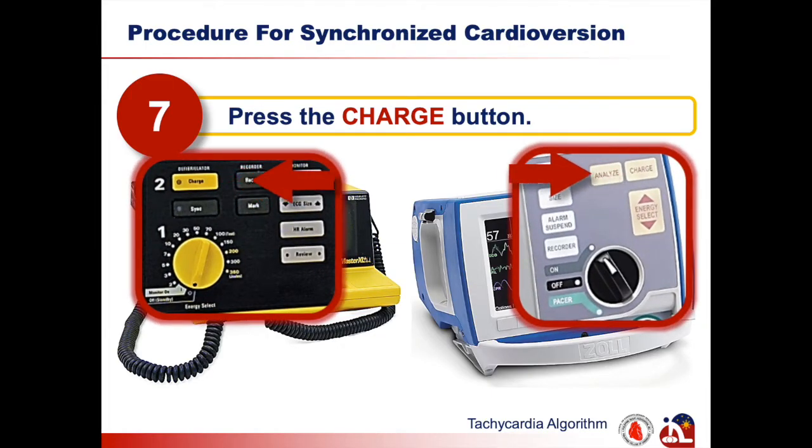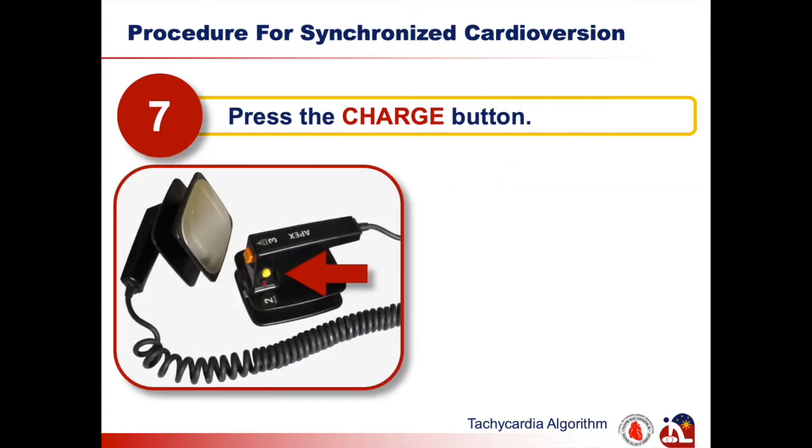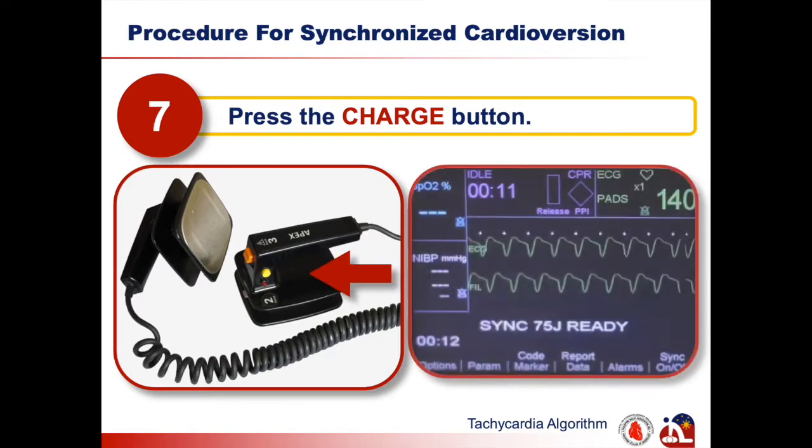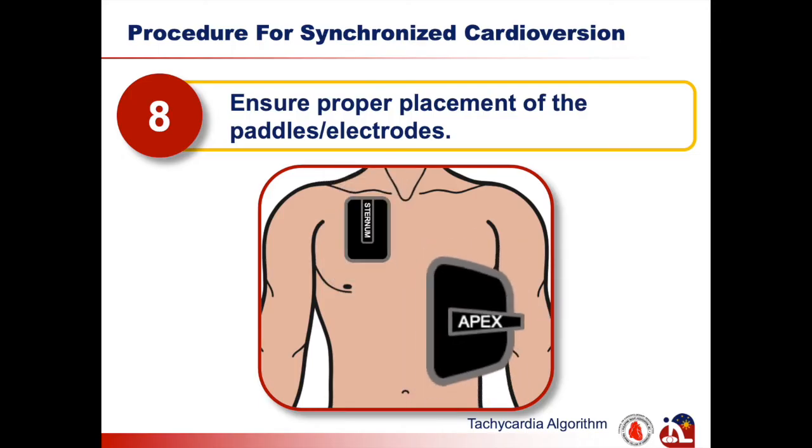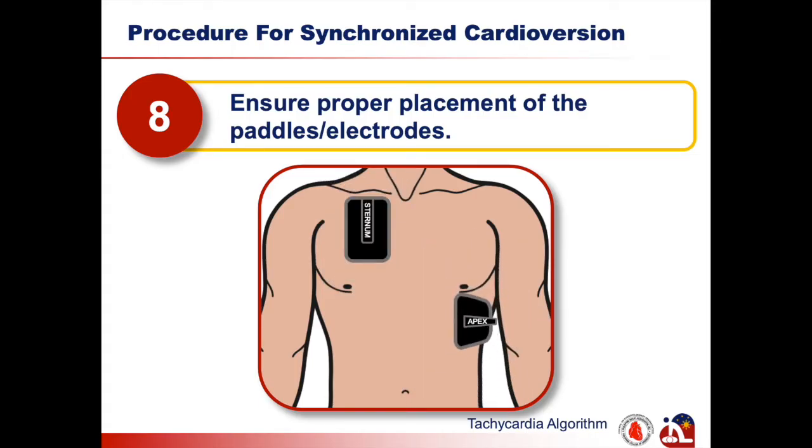You can also press the yellow button on the paddles to charge. Once charged, the word Ready will be displayed on the screen. Ensure proper placement of the paddles and electrodes, following these anterior lateral positions.